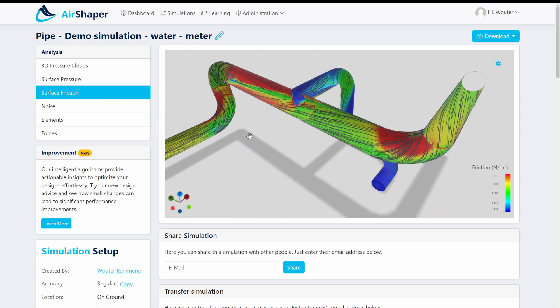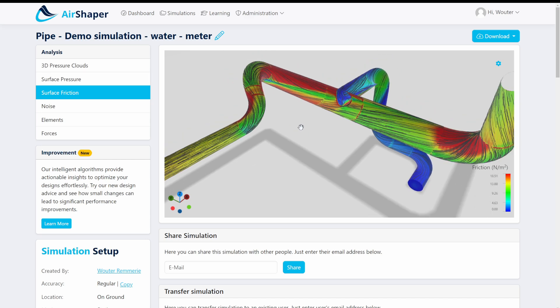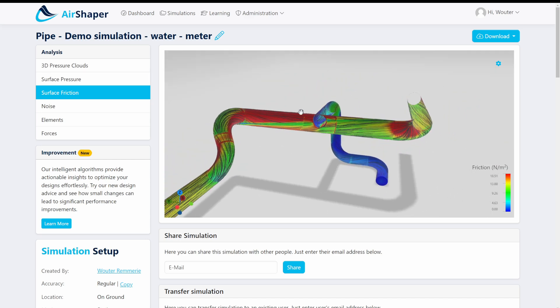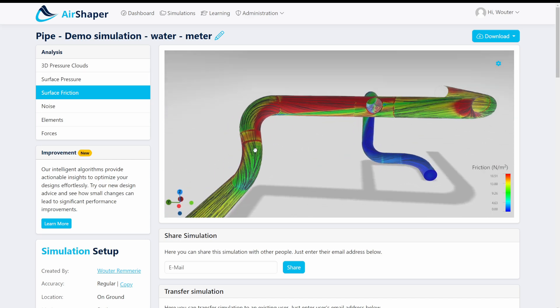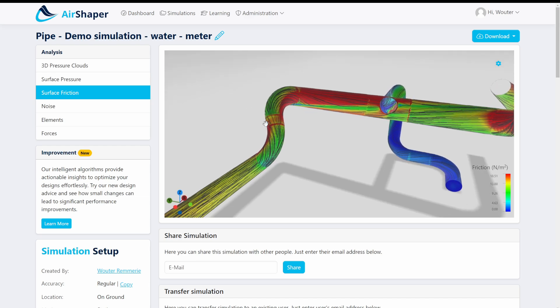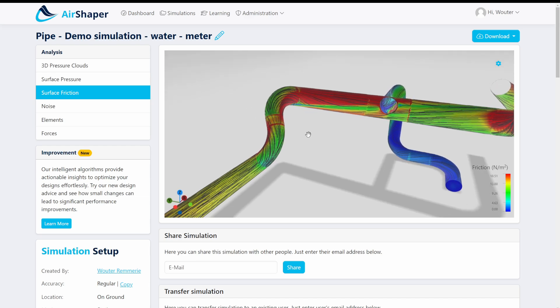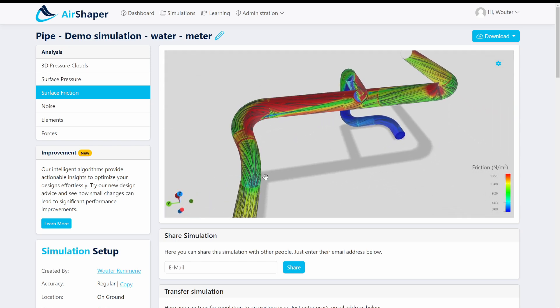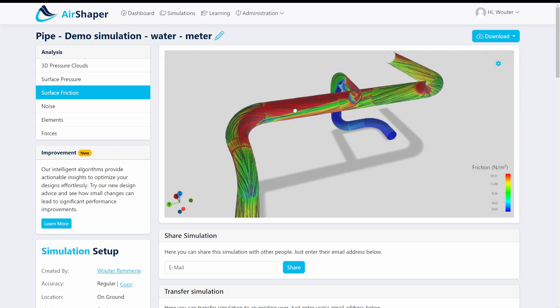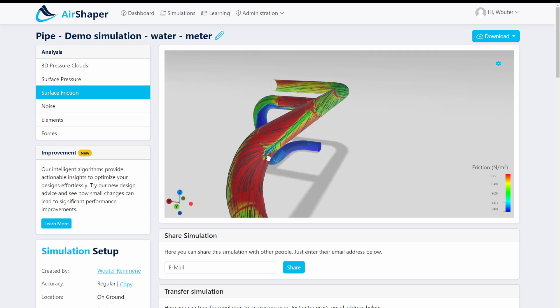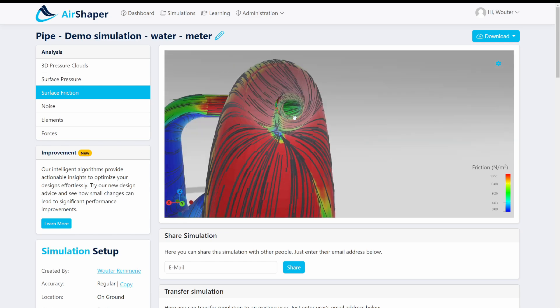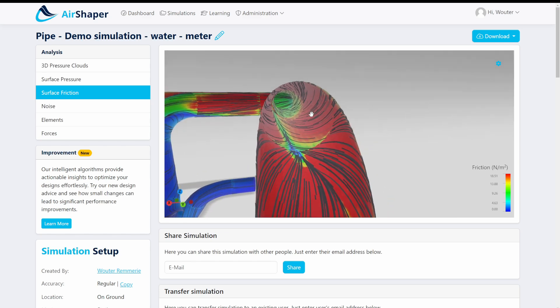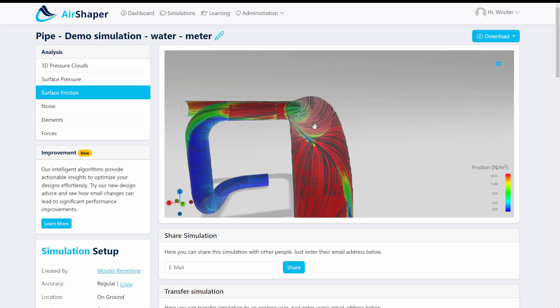And then if you look at the surface friction this is where we can actually analyze the surface friction on different elements of the pipe. Again you see these ringed elements because these are edges in the 3D model but what we see here is that because you get this swirl in the flow you get very asymmetric pressure patterns. There's a bit of flow separation here happening which travels all the way downstream. You can see the swirl of the flow creating higher friction on one side.